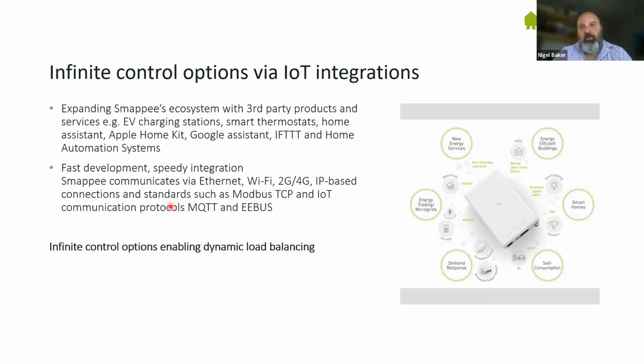The reason we chose the Modbus protocol is that it's pretty generic and very commonly used for collecting energy data, and it's very easy to integrate. We've got the Modbus registers, and we do Modbus TCP, which is pretty simple. The beauty of that is you get access to the data on the app and the dashboard, and you can also have access to the data on your SCADA system or your building energy management system. You can do pretty much all the controls, the load balancing, and the switching through the Modbus protocol as well.